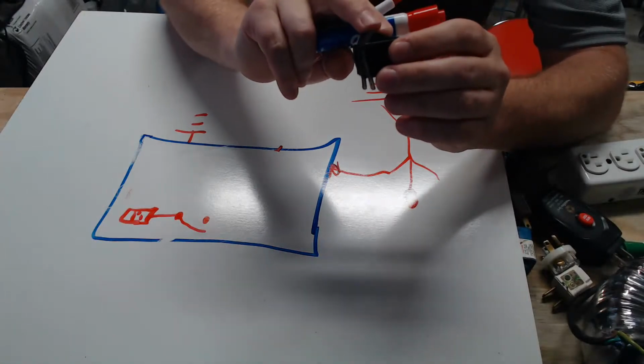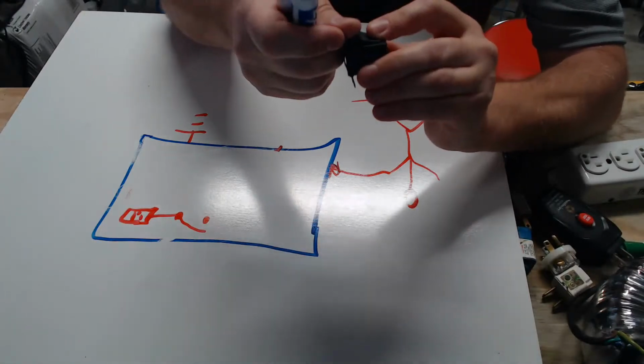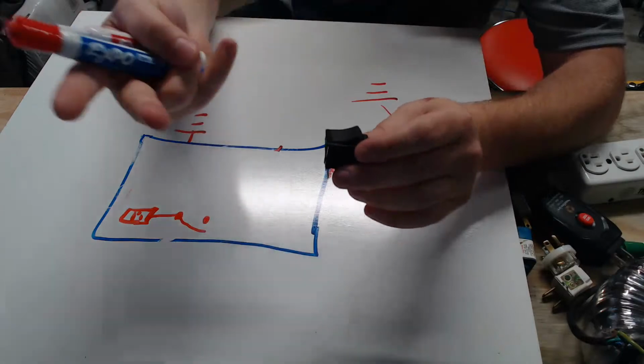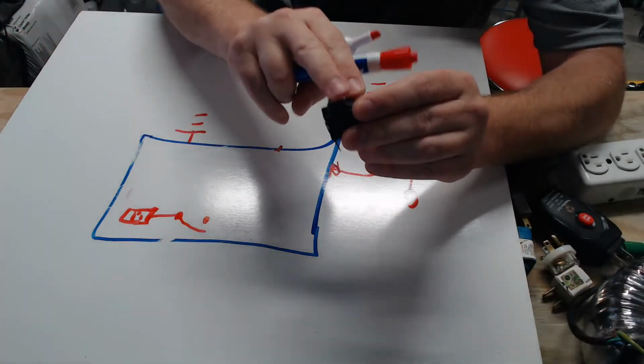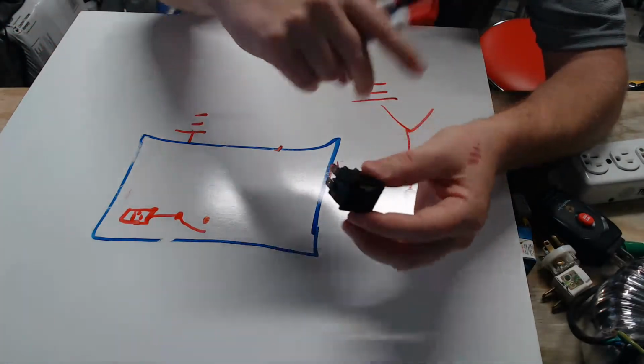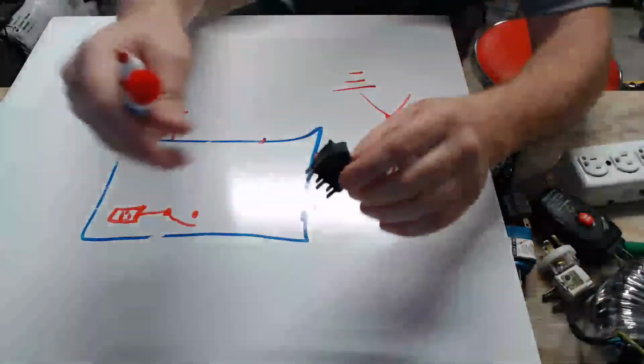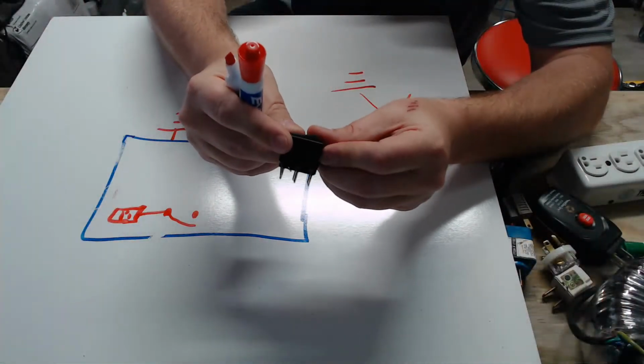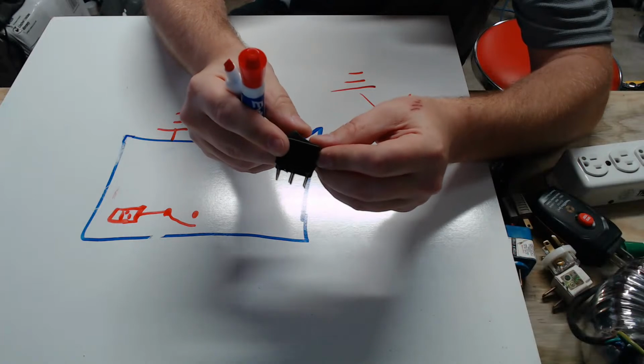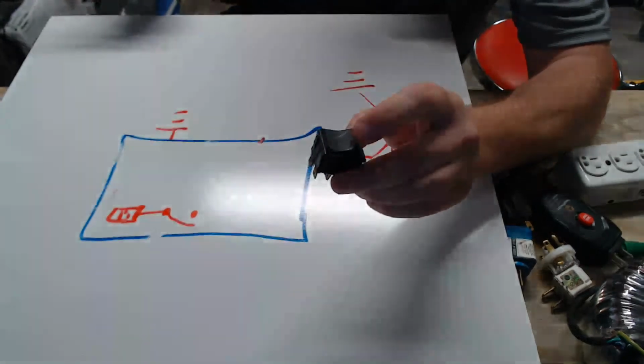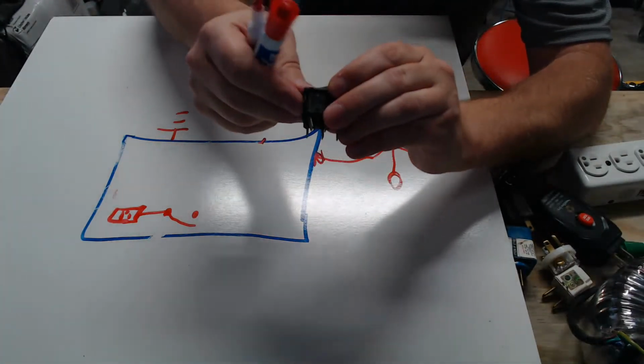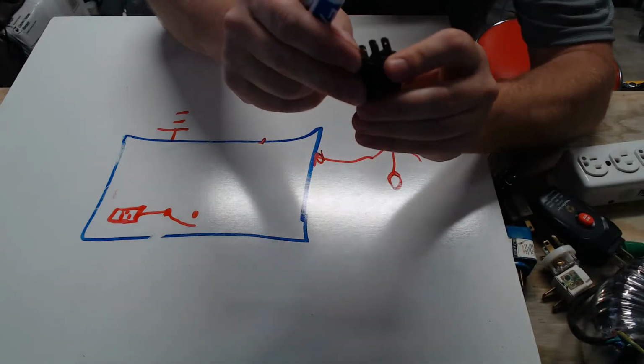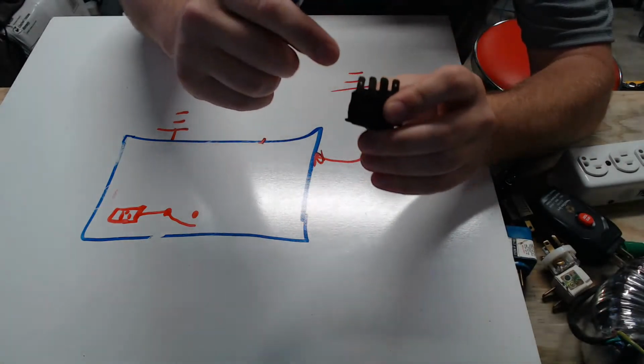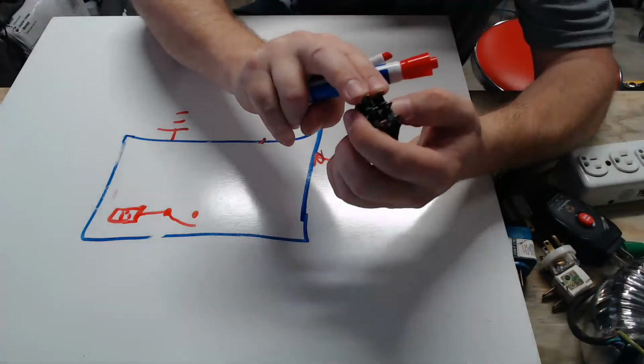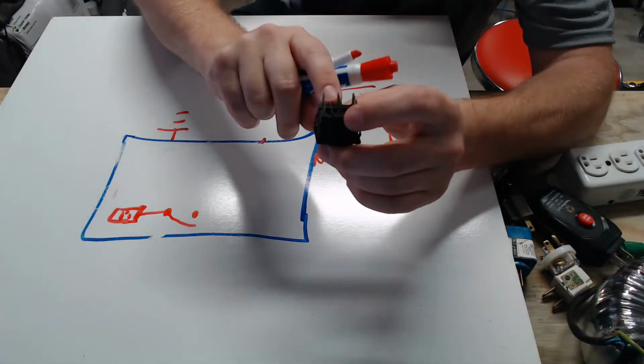Okay, so a double pole, double throw is when you have a middle position and you flip it one way and that reverses the polarity, or you flip it this way and it changes the direction of the wires. See that? So this is a single throw because it pops over in one direction only. It's on or it's off. All right. It's a double pole because you have both line and neutral, which are being switched.